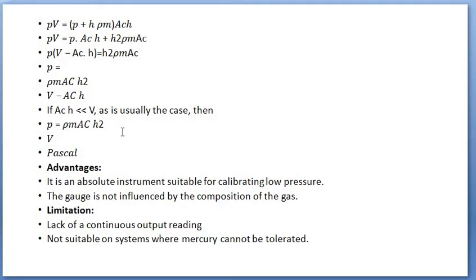So this gives the pressure in Pascals. Advantages: it is an absolute instrument suitable for calibrating low pressure, and the gauge is not influenced by the composition of the gas. Limitations: lack of continuous output reading, and it's not suitable on systems where mercury cannot be tolerated.